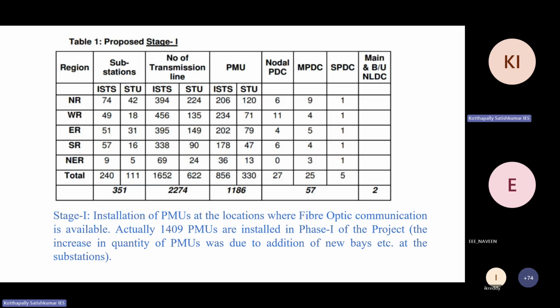So finally, out of 1186, they commissioned 1409 PMUs in phase 1. This phase 1 is basically where the CERC gave permission wherever fiber optic communication is available, because now you can understand the quantity of data and the speed of data. To deal with the speed, accuracy, and such a large quantity of data, you need a fiber optic communication network. So stage 1 of phase 1 is implemented wherever communication already exists. They just installed the PMU, since fiber optic communication was already there at those substations. Using this fiber optic communication, the PMU transfers data to the PDC. PDC is nothing but phasor data concentrator, a server which stores the data of the PMU, and it has some analytics. This analytics takes the data from the PDC, analyzes it, and gives the outcomes.